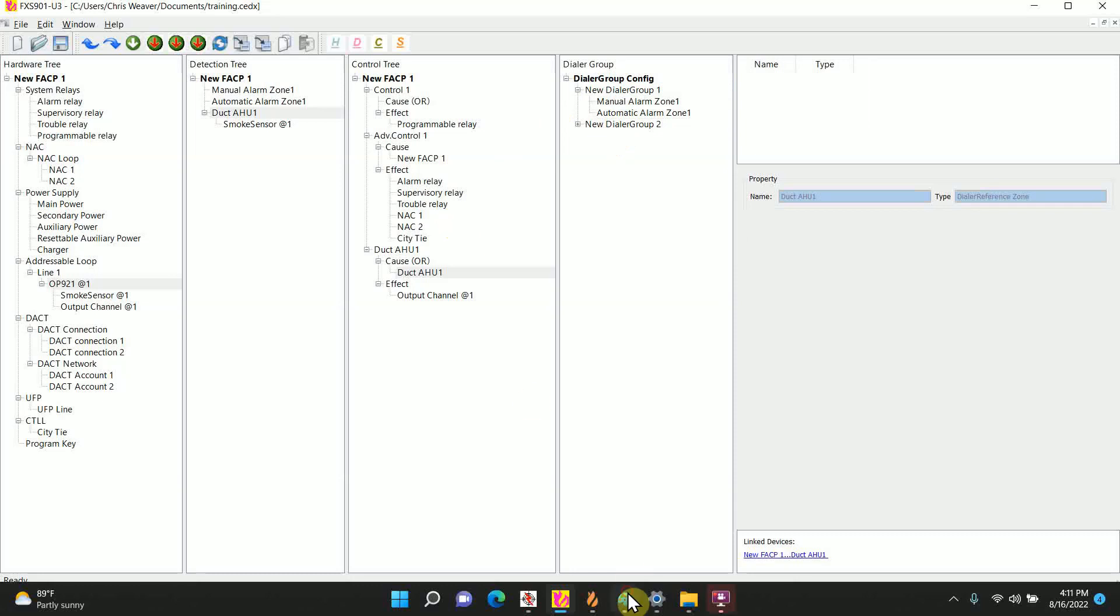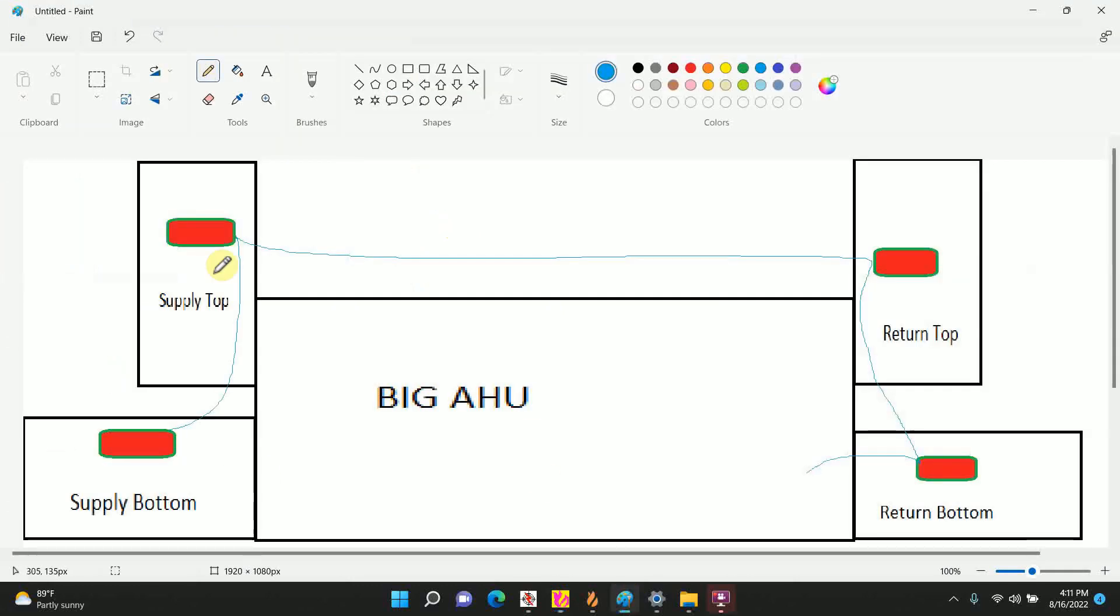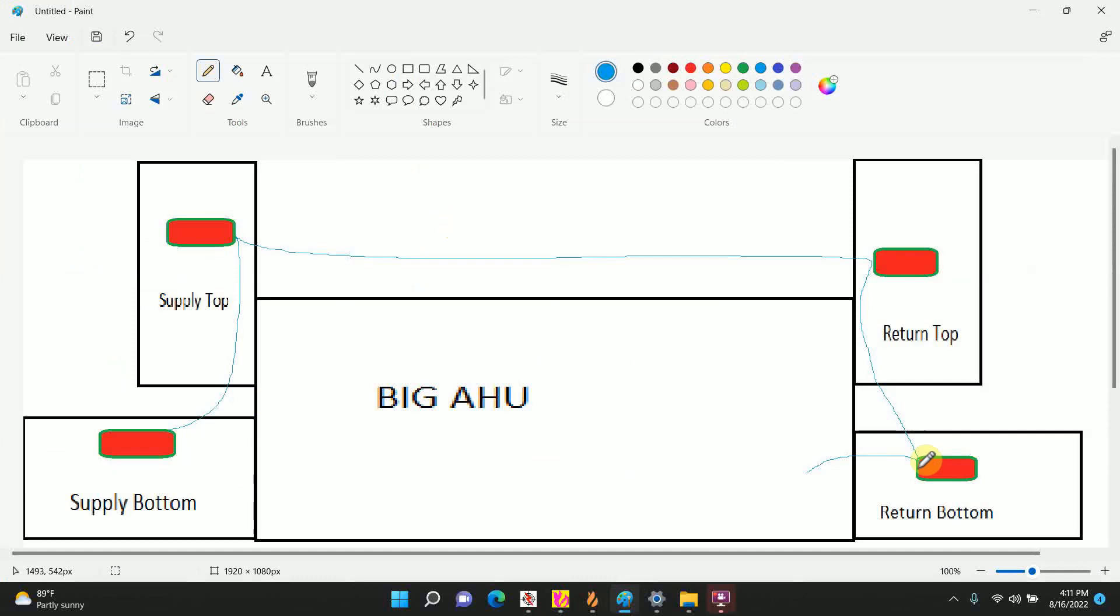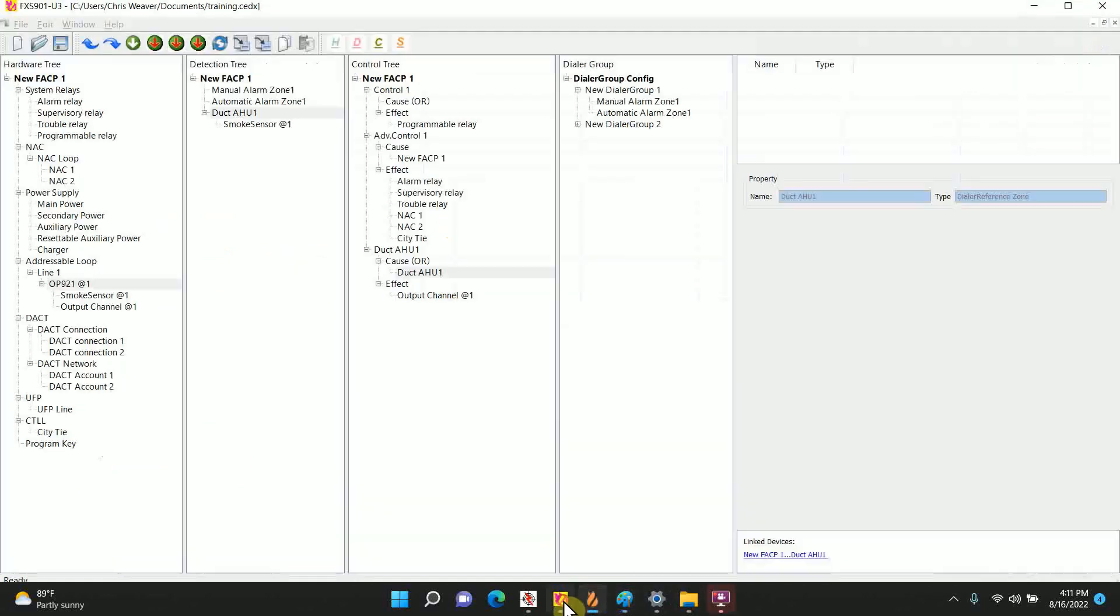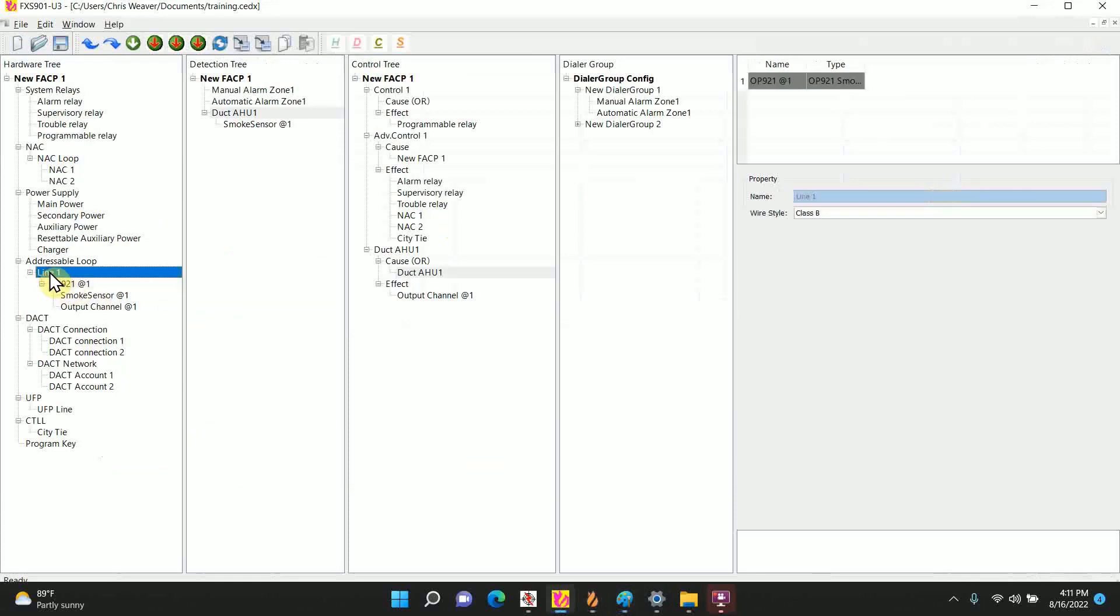This is good for the single ones, but in the picture example we actually got 4 duct detectors on one air handler unit. If supply bottom goes into alarm, we need the return bottom to trigger its relay because that's where we have the closest disconnect. So to do that, let's go back to the thing here. I already added one, let's add three more.